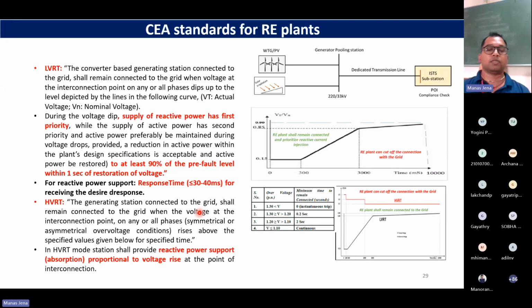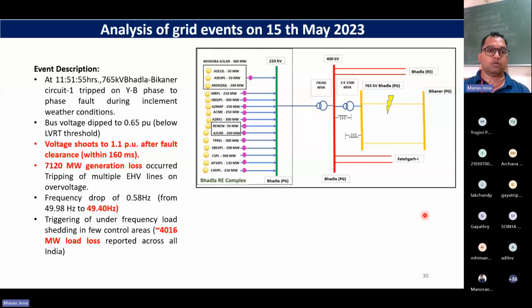I am setting the standard first before discussing the use cases. We should understand that in LVRT, I need to provide VAR support. VAR support is given priority, and megawatt should go down. In HVRT, I am supposed to absorb VAR. Of course, there are limits given beyond which I should trip. Once the standard is fixed, we should understand whether it is followed.